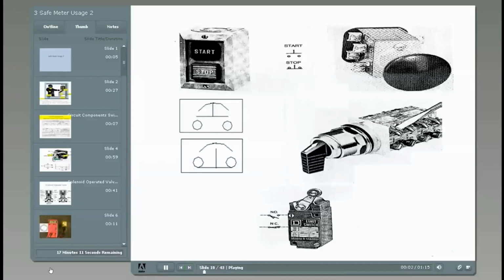Stop switch on the left and an E-stop switch on the right. The start switch is normally open, NO, and the stop switch is normally closed, NC. The operators on the stop and start are spring-loaded and they are actuated momentarily, and only as long as they are being depressed. The E-stop switch is spring-loaded normally closed, NC. Some E-stop switches are push-pull.